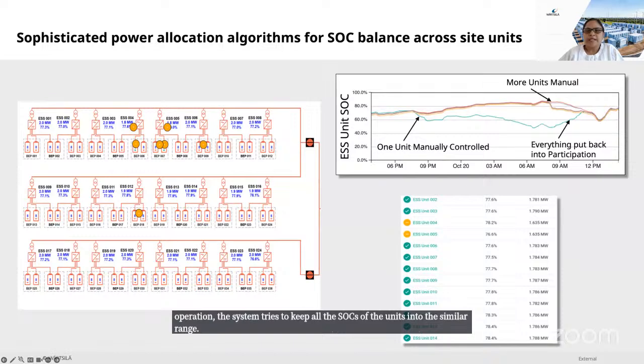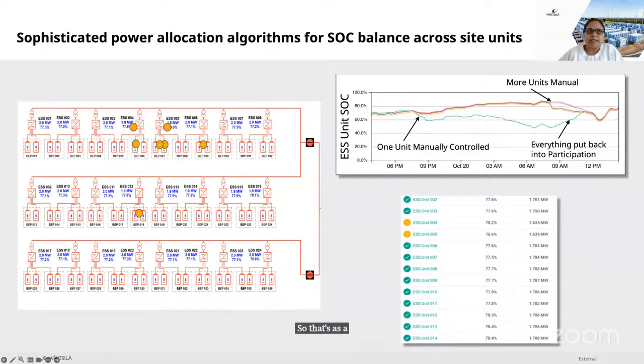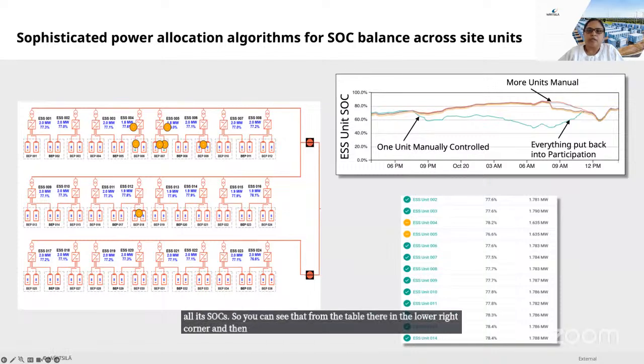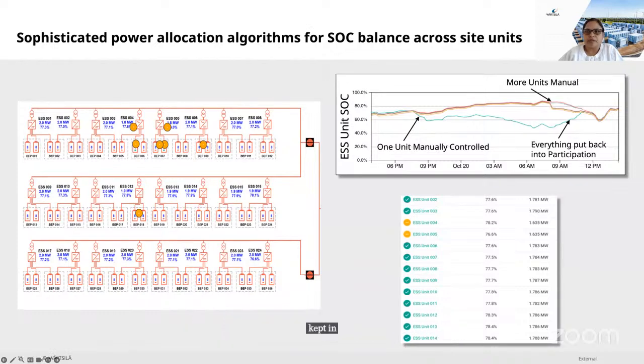As a result of this SOC-balanced algorithm, the units keep their SOCs in a similar range. You can see that from the table in the lower right corner, and from the SLD, that all those units' SOCs are kept in a similar range, within the allowed dead band of 2 or 3%.